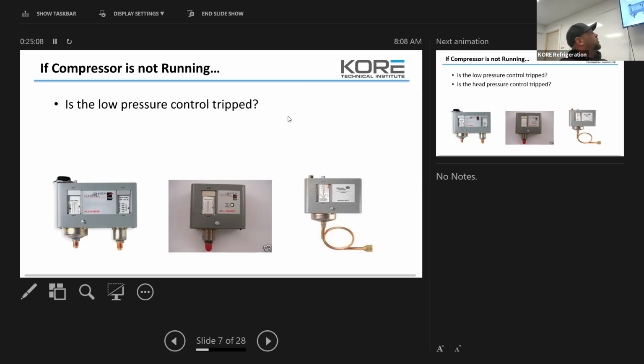This is a low pressure control trip. Okay. This is a dual pressure control. That's a head pressure control with a manual reset, so you're actually going to have to push the button. Okay. We'll talk about button pushers here shortly, how I feel about that.